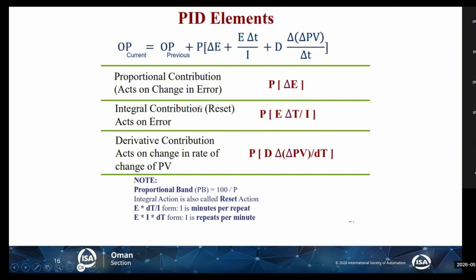And this is our integral contribution, and this is our derivative, as we explained before. You can also see this note on proportional band. As I said, in some DCS systems it is not proportional gain but proportional band, PB, which is nothing but 100 divided by P. With proportional gain, the higher the number, the more aggressive. With proportional band, the lower the number, the more aggressive. So it is the opposite, but it's the same action, just how manufacturers represent it.